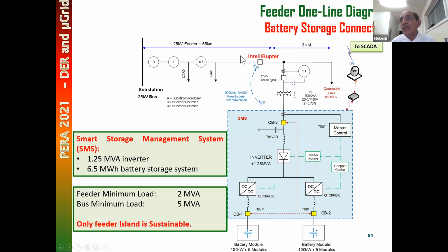So for a fault current here, the desensitization was so small that there was no need to put an impedance grounding here. The fault current from here was not strong relative to this strong source for a fault here. So there was no need to worry about ground desensitization or phase desensitization. So we put a new PD here, new protection here, and this is a device called an IntelliRupter.